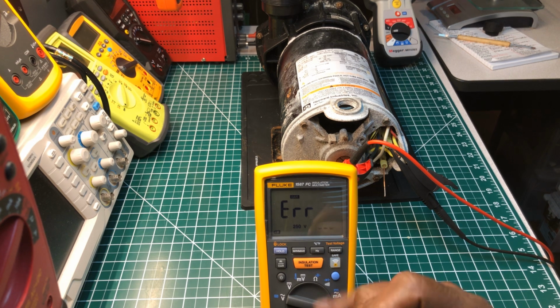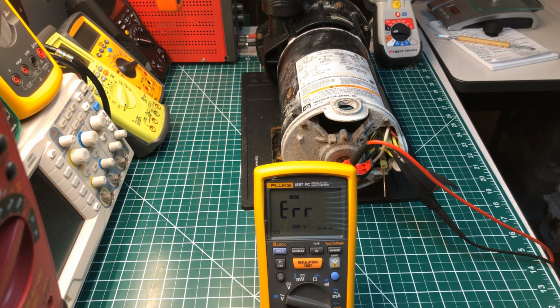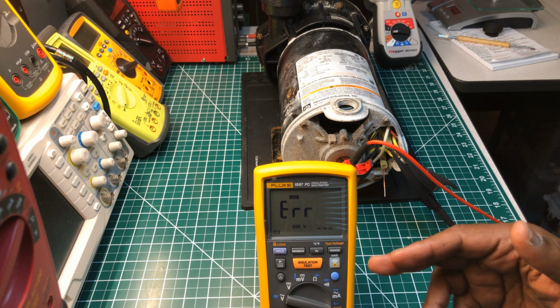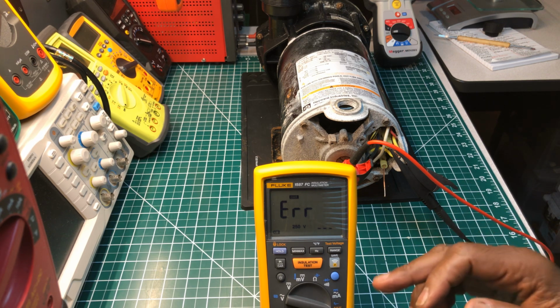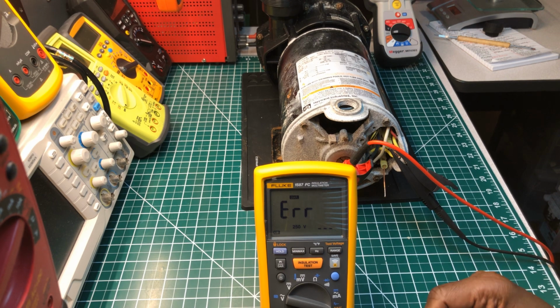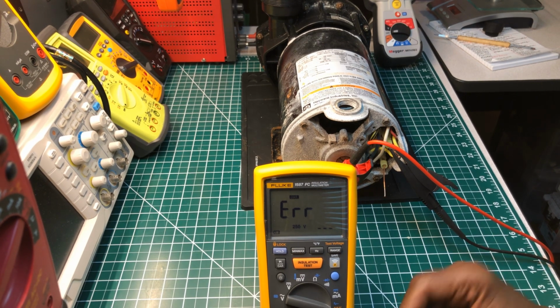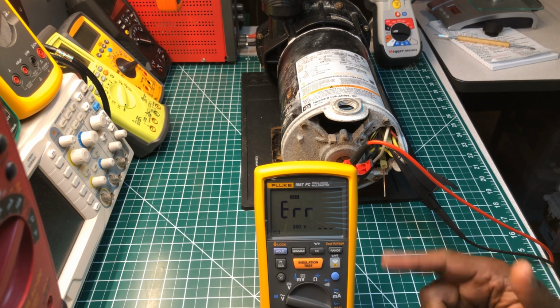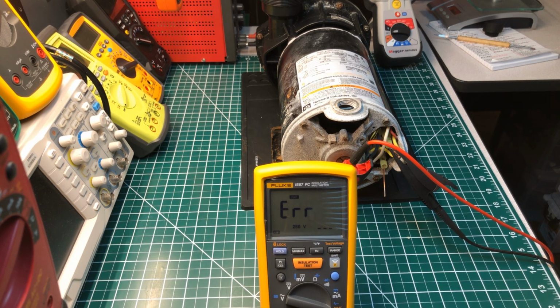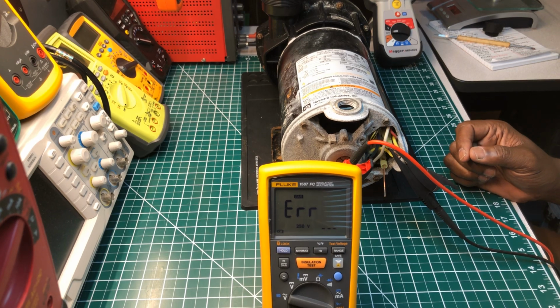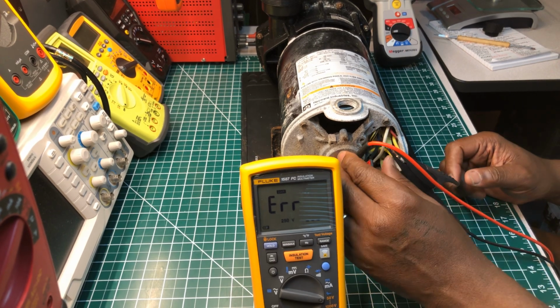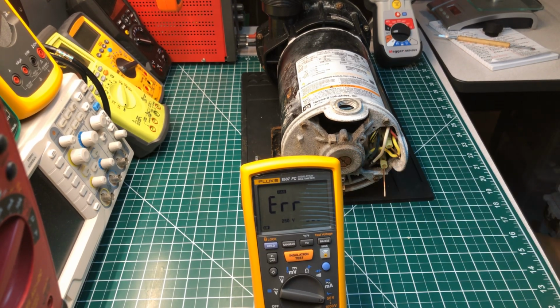So it may give me that ERR, and that only pops up when it's a greater value than what this meter can display on that test voltage. Okay, so it's saying it's more than 275 megaohms. So they're saying this motor is good. So let's do the MEGGER.